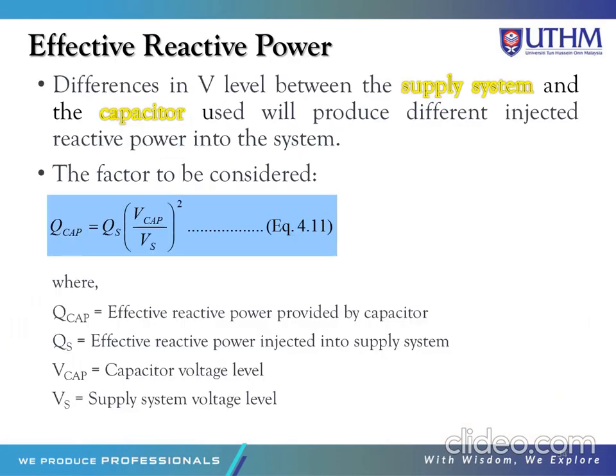This is the effective reactive power. Differences in V level between the supply system and the capacitor used will produce different injected reactive power into the system. So the factor to be considered is given by this formula to calculate the Q capacitor, where Q cap is the effective reactive power provided by the capacitor, QS is the effective reactive power injected into the supply system, VCAP is the capacitor voltage level, and VS is the supply system voltage level.